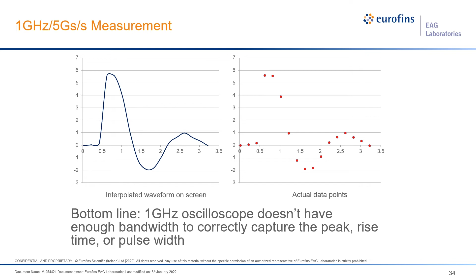So what's the problem? The problem is it's an interpolated waveform. The scope is making up that waveform using the data points you see on the right, those orange data points. That's not a lot of data points, and the bottom line is there weren't enough of them to accurately determine the peak, rise time, or pulse width.